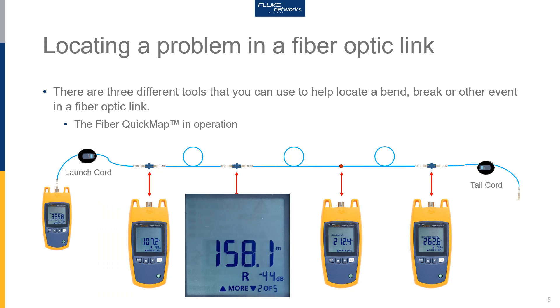The next event is occurring at 158 meters. The reflectance is minus 44 dB, which indicates this is most likely a connector — it's the second event of five. For reflectance, I set my instrument at minus 45 dB plus or minus 1 dB, so this minus 44 dB reading is perfectly okay.